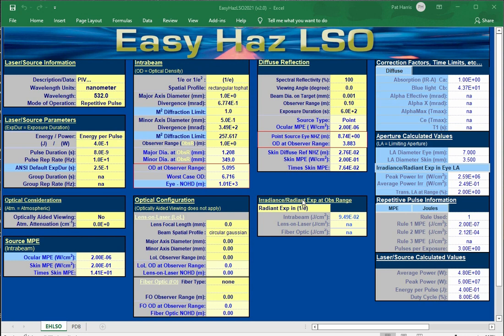If you look at table 1 in the standard, you'll see something called Tmin. And for this wavelength, 532, Tmin is 5 microseconds. What we mean by that is any two pulses that arrive within 5 microseconds, within Tmin, are treated as a single pulse.